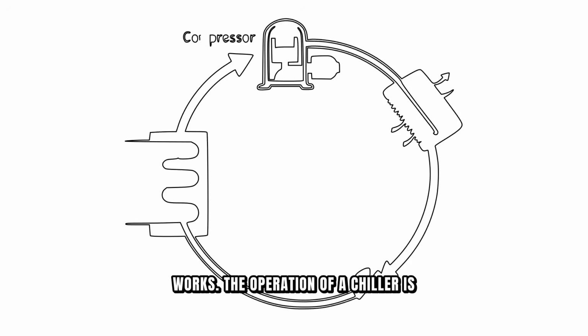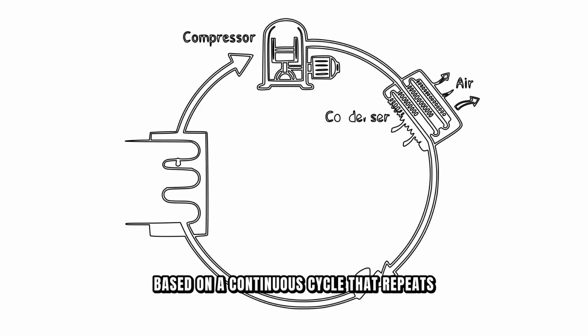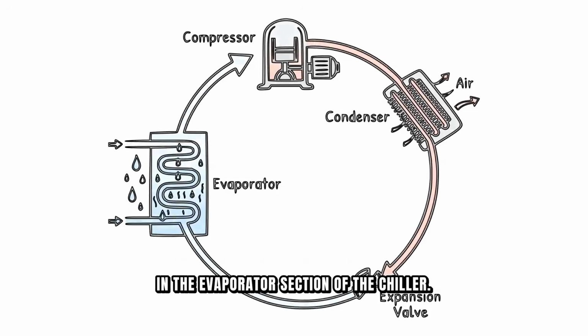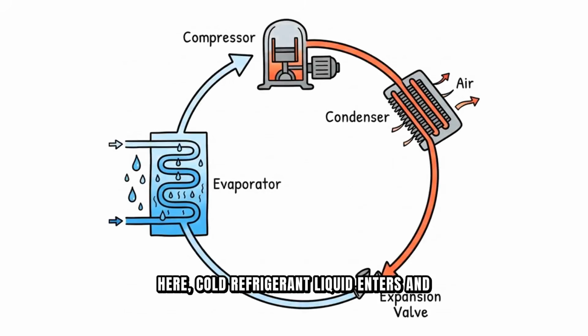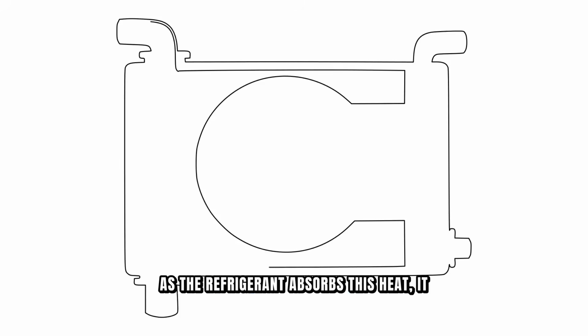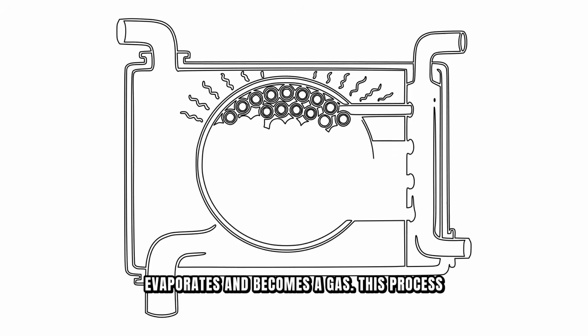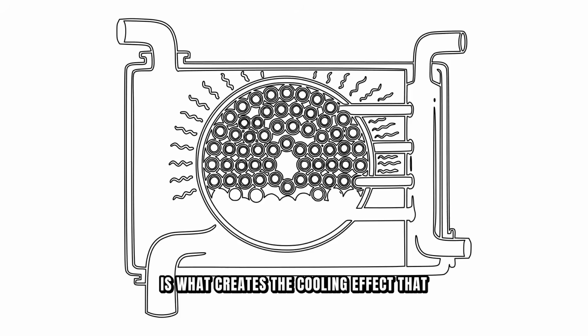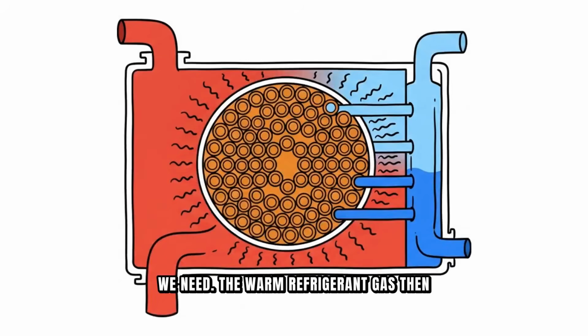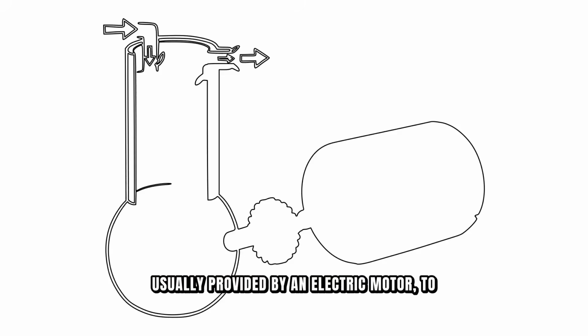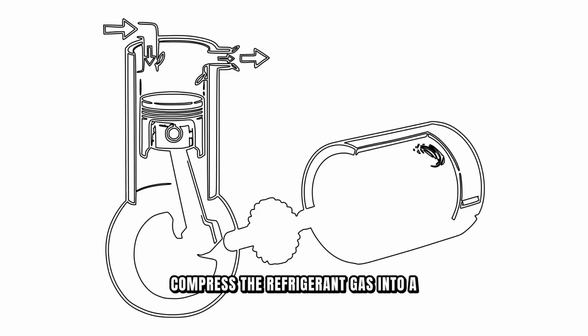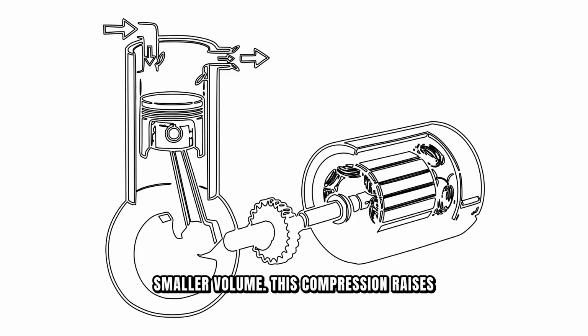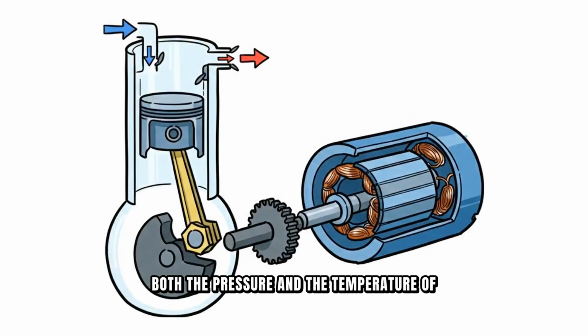The operation of a chiller is based on a continuous cycle that repeats many times per minute. The cycle begins in the evaporator section of the chiller. Here, cold refrigerant liquid enters and absorbs heat from the water that flows through the chiller. As the refrigerant absorbs this heat, it evaporates and becomes a gas. This process is what creates the cooling effect that we need. The warm refrigerant gas then travels to the compressor, which is essentially the heart of the entire system. The compressor uses mechanical energy, usually provided by an electric motor, to compress the refrigerant gas into a smaller volume. This compression raises both the pressure and the temperature of the gas significantly.